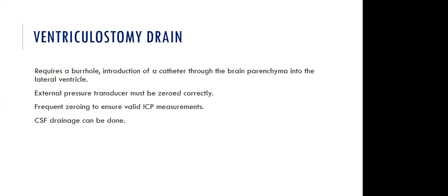It has some associated complications, which may range from intracranial hemorrhage, because it has to do with a surgical procedure where the catheter is passed into the ventricle. The risk of infection is also high, and the external drain must be at a particular level. The transducer must be at the level of the external auditory meatus, and zeroing must always be done to have valid intracranial pressure measurements.